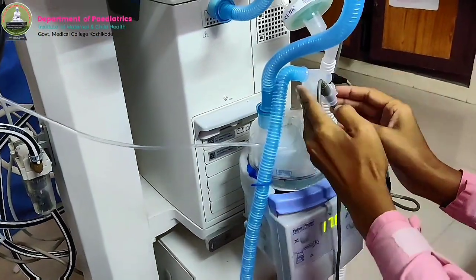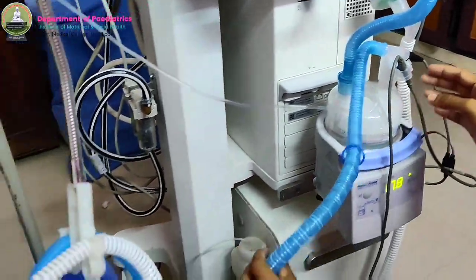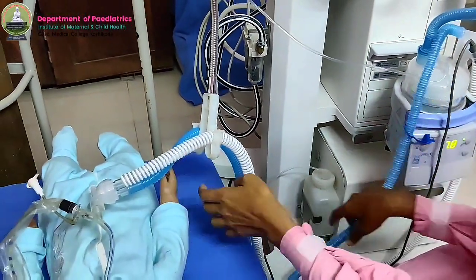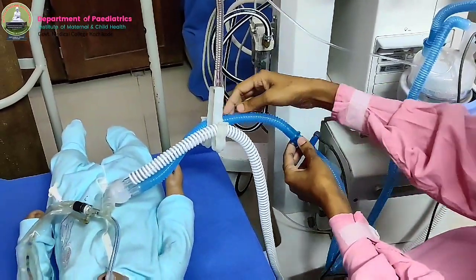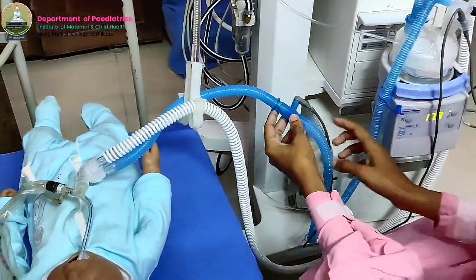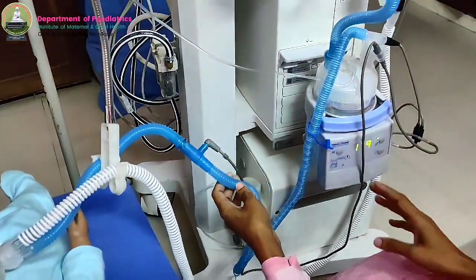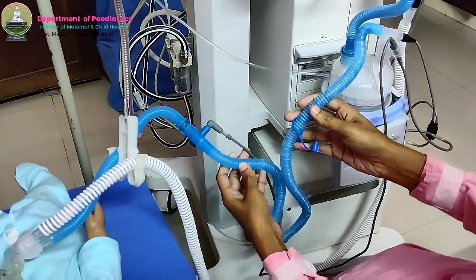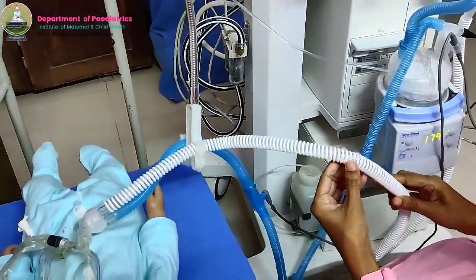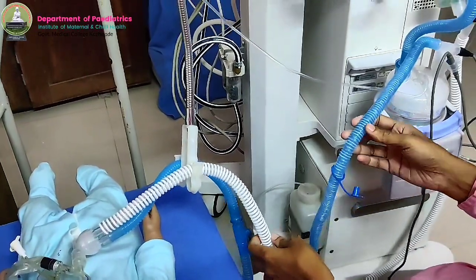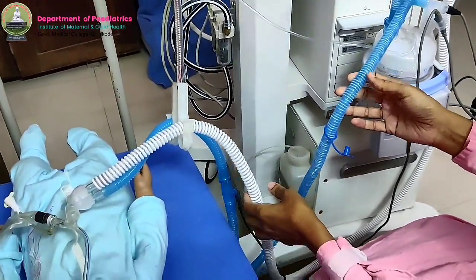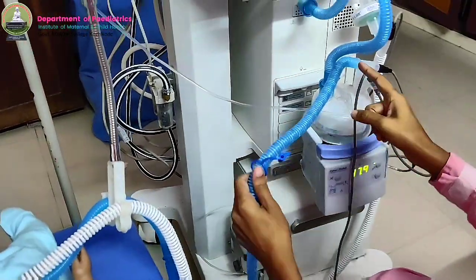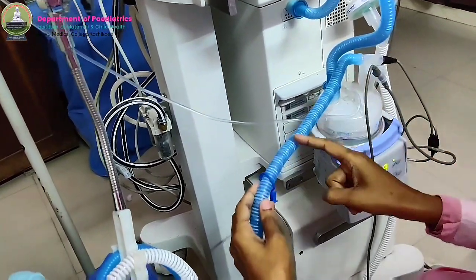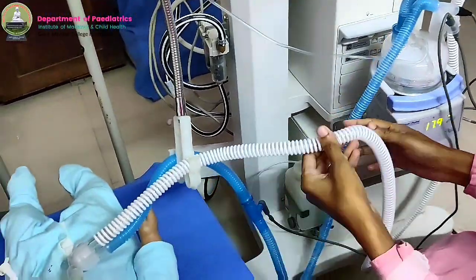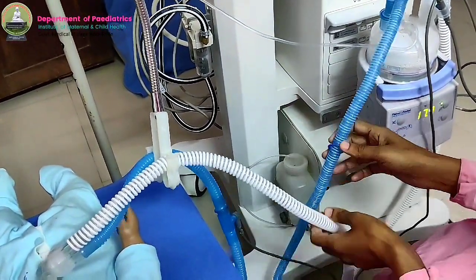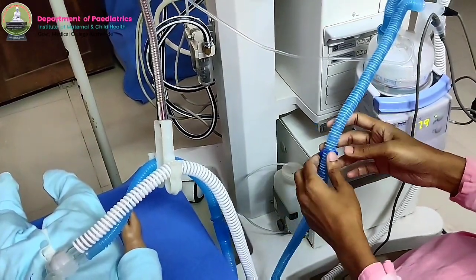Then the next connection is from the humidifier to the patient. This is that connection, and there is a short 30 cm segment here. This is the inspiratory limb. By convention, the inspiratory limb is color coded as blue and the expiratory limb is white. This is a dual heated humidifier ventilator circuit. What does that mean? There is a heating wire going inside the inspiratory limb as well as the expiratory limb. That is what is meant by dual heated ventilator circuit.